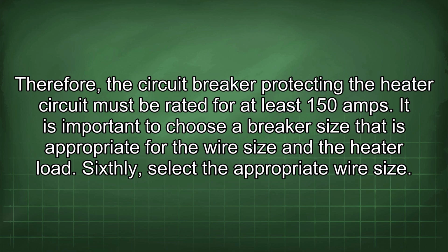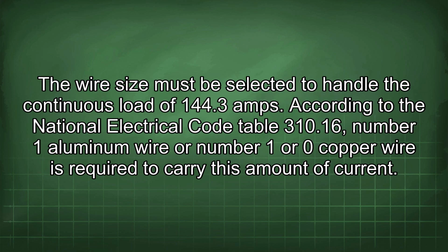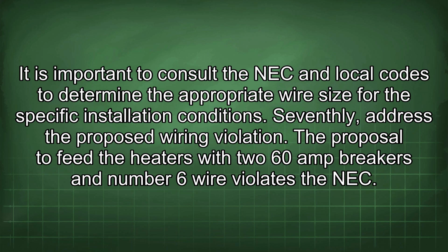Sixthly, select the appropriate wire size. The wire size must be selected to handle the continuous load of 144.3 amps. According to the National Electrical Code Table 310.16, number 1 aluminum wire or number 1 or 0 copper wire is required to carry this amount of current. It is important to consult the NEC and local codes to determine the appropriate wire size for the specific installation conditions.